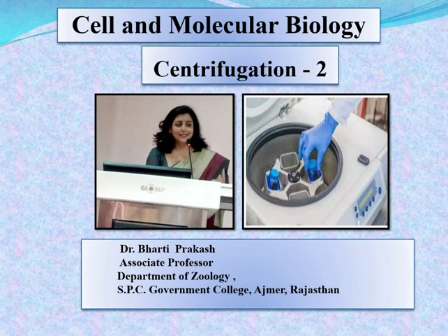Every centrifuge contains a spinning vessel. There are many centrifuges depending upon the use. For example, a perforated rotating drum in a laundry that throws off excess water from the clothes is also an example of a type of centrifuge. The basic centrifuge components include an electric motor, a shaft, rotor heads on which the centrifuge head turns, and a motor drive assembly.